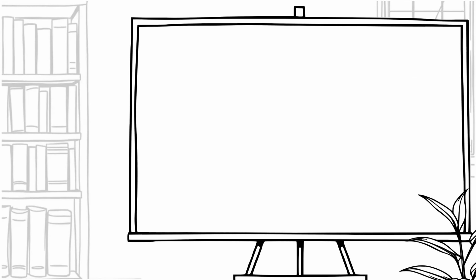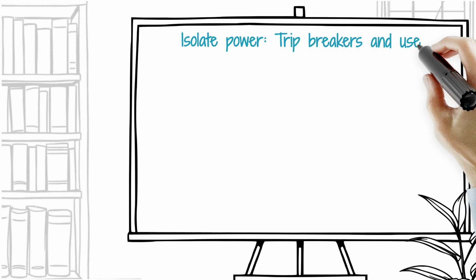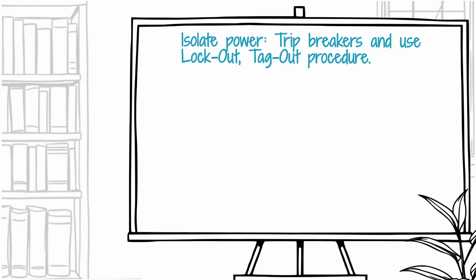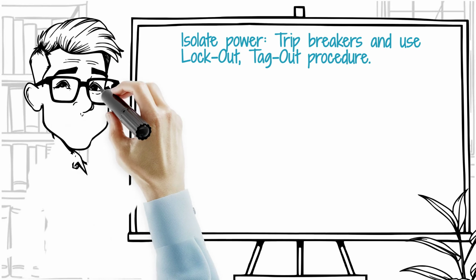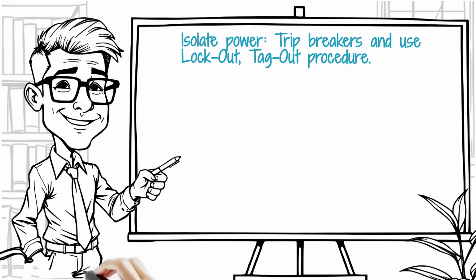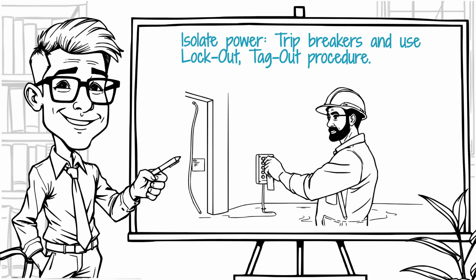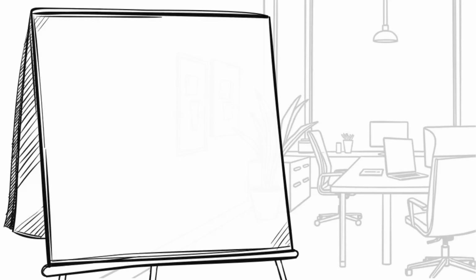Immediately trip the main circuit breaker feeding that section of the ship's electrical system, or trip the breaker specific to the submerged equipment. Use a lockout, tag-out procedure to ensure the power cannot be accidentally restored while the area is unsafe. The second step is personnel safety assessment.